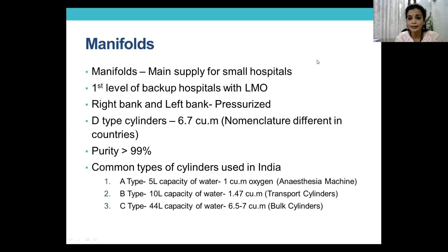Now, this is typically a question that is asked often, and recently I had this 2 days back. Somebody just sent a gauge and the type of cylinder there and asked, I'm going to transfer my patient. How long do you think the cylinder is going to last? Now, if you look at the dial, the gauge reads the pressure. And here this person told me it's about 150 liters of oxygen. No, the gauge there reads the pressure. The full cylinder pressure is about 138 bar. And if you read this gauge, it is about 130 bar, which shows that the cylinder is about 94% full. So 94% full, it means it will have about 6,110 liters of oxygen gas.